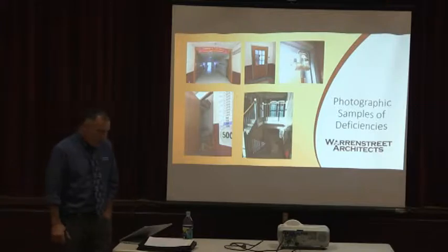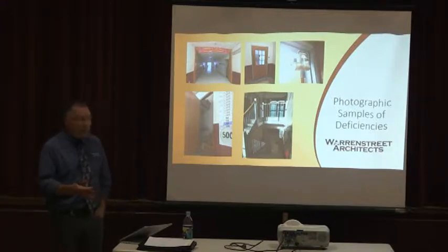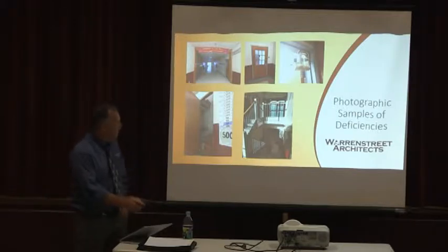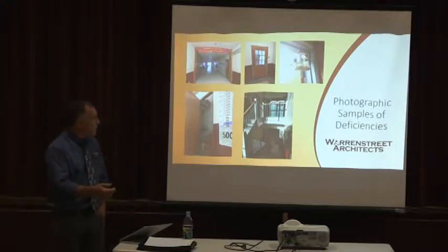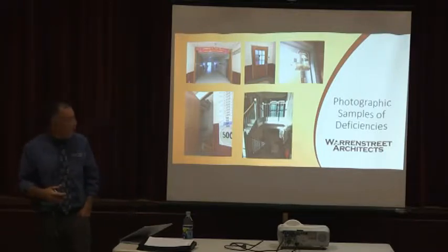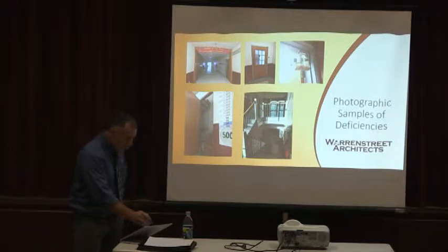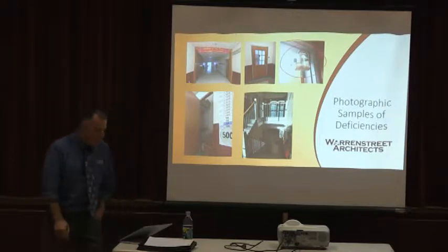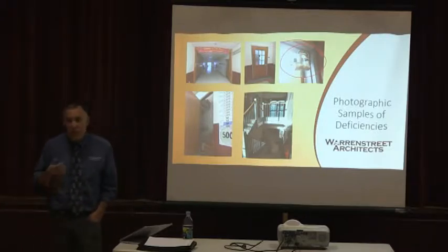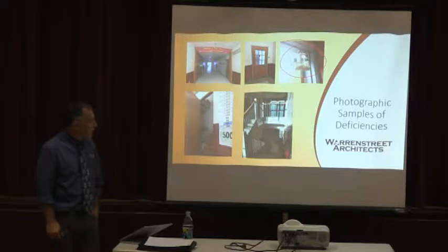This is an example of some of the life safety code issues that I found. Corridors with coats being stored in them, that's not allowed by code. Doorways that don't have the correct fire rating on them. Really old devices that probably still work fine, but at some point they're not going to work and need to be replaced. Just due to the age, they should be replaced.